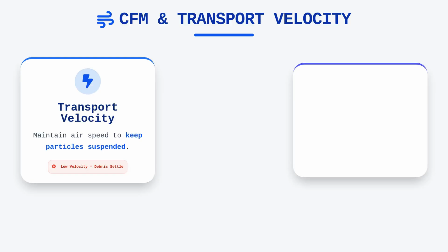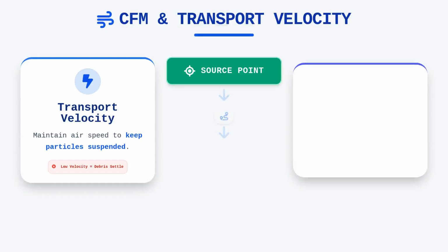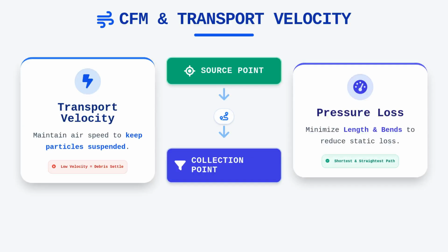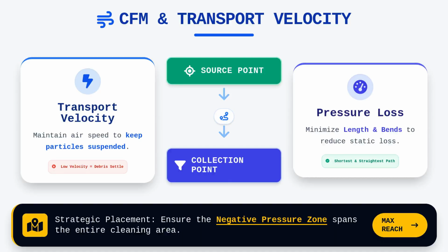When selecting our vacuum hose, we must account for the inverse relationship between hose length, diameter, and the static pressure loss of the system. A longer hose with multiple bends drastically increases resistance, which forces the NAM to work harder to maintain the required CFM. Always aim for the shortest, straightest hose path possible from the cleaning site to the collection point to minimize these losses. Furthermore, the vacuum collection points must be strategically placed so that the negative pressure zone spans the entire area we intend to clean while maintaining enough strength to pull debris from the most remote reaches of the ductwork.